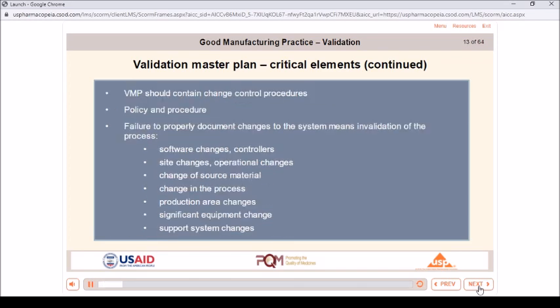Validation Master Plan, critical elements continued. VMP should contain change control procedures, policy and procedure. Failure to properly document changes to the system means invalidation of the process. Software changes, controllers. Site changes, operational changes. Change of source material. Change in the process. Production area changes. Significant equipment change. Support system changes.